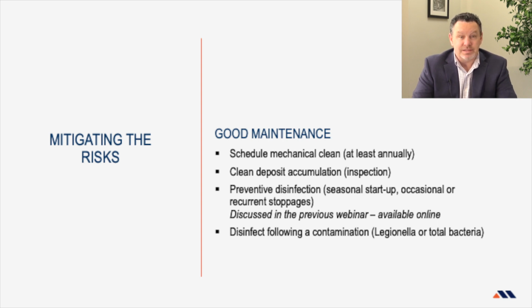Major importance is to clean and disinfect the cooling tower systems at least once a year. That includes the basin, the fill, the distribution systems, the heat exchangers, most of the piping if you can, or to dryness when you lay it up. Those are basic levels you need to do every year.